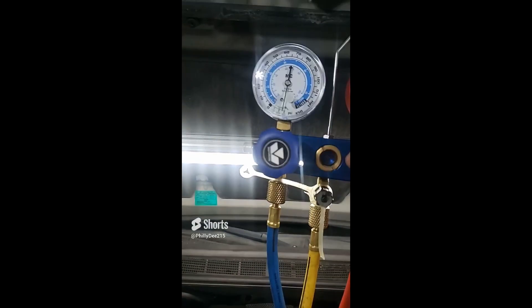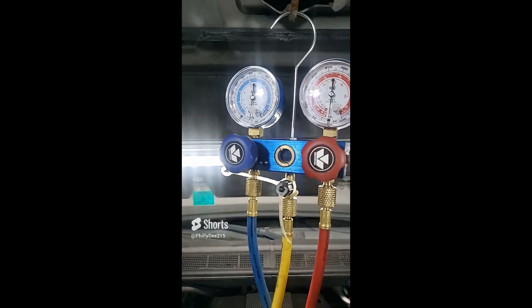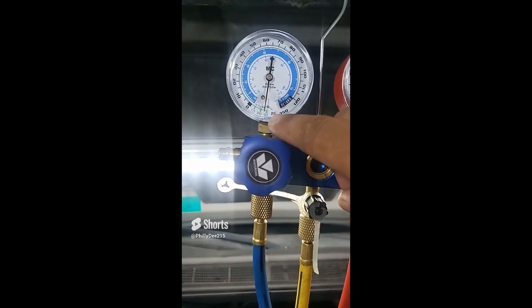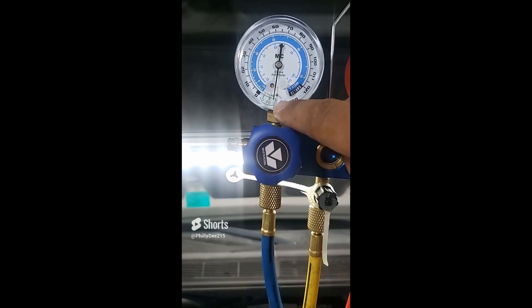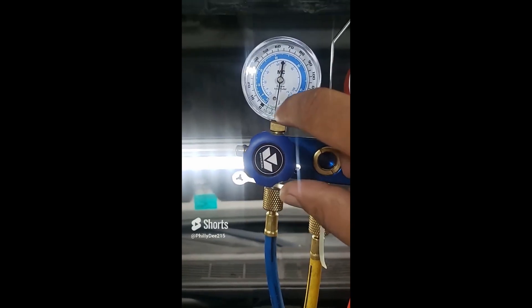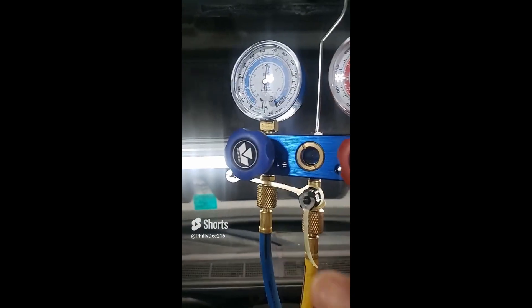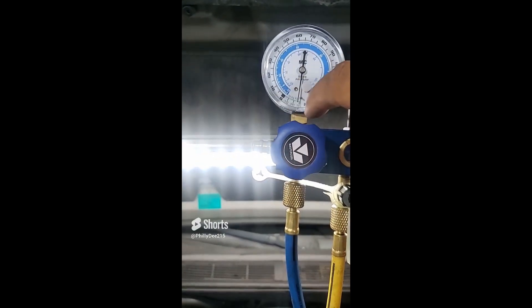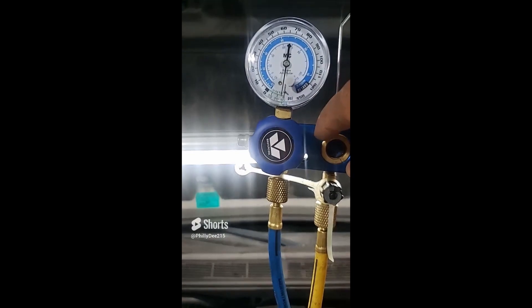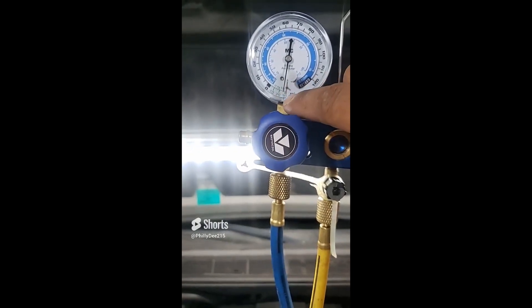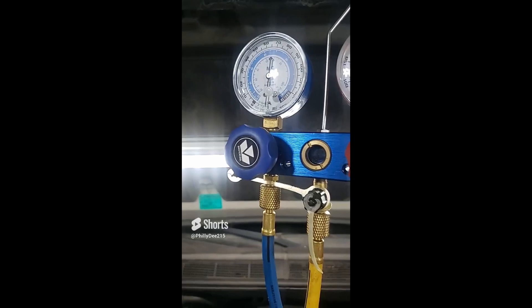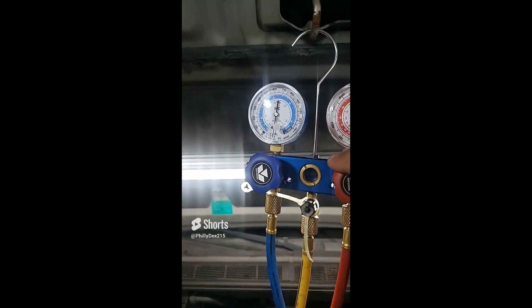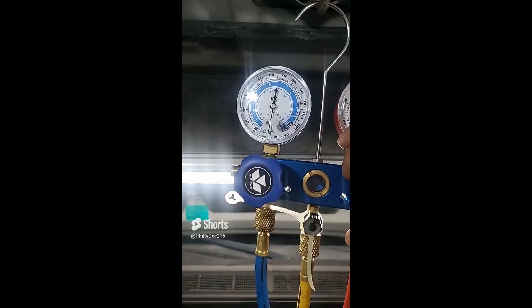You also want to vacuum your system out to confirm that there's no leaks in the system. So once you get your system vacuumed down to 28 to 30 inches of mercury, you let it sit before you open up any of the valves. You just let it sit because if it drains back down, if it goes back this way, that means you have a leak. If it's still sitting there, that means you don't have a leak. So you want to make sure you don't have moisture in your system, and you also want to make sure your system doesn't have a leak.